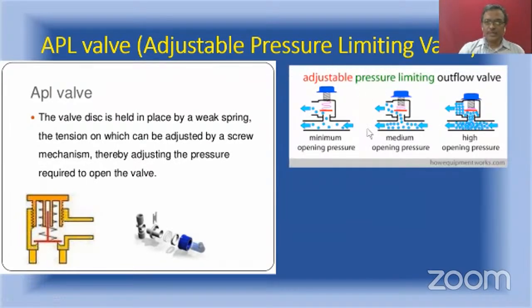Look at this picture on the right side. So when the valve is fully open, the disc can be easily opened up by the minimum pressure developed in the circuit. So whenever the patient is spontaneously breathing, the APL valve should be fully open. But the disc will remain closed in the aperture, and will be raised by a slight increase in pressure inside the circuit. And when controlled ventilation is done, usually the valve is in the partially closed position.